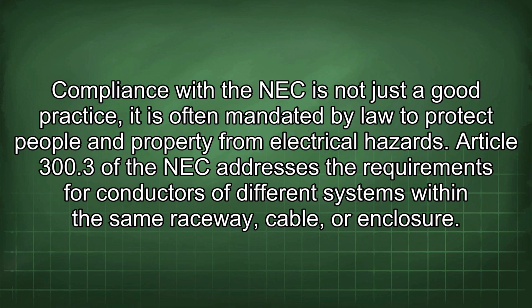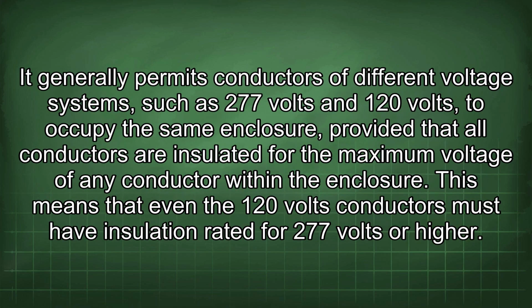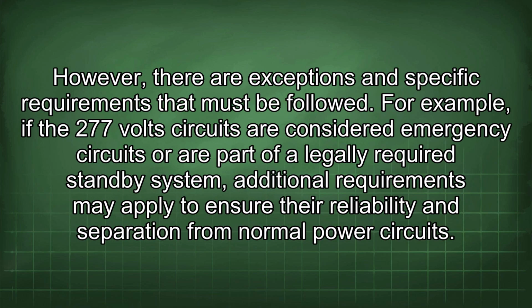raceway, cable, or enclosure. It generally permits conductors of different voltage systems, such as 277 volts and 120 volts, to occupy the same enclosure, provided that all conductors are insulated for the maximum voltage of any conductor within the enclosure. This means that even the 120 volt conductors must have insulation rated for 277 volts or higher. However, there are exceptions and specific requirements that must be followed.